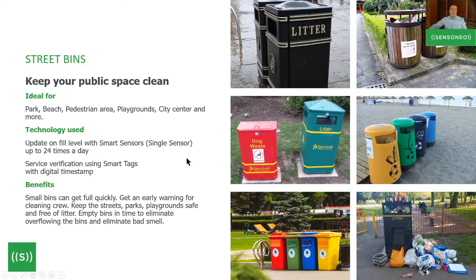Usually, we use single sensor for these use cases, in case there is availability of certain low power network, meaning our sensors support Sigfox, LoRa, NB-IoT connectivity. We also do support Bluetooth mesh networks, so streaming over advertising over Bluetooth. That's also possible. So a single sensor can support all of these. If there is a country that does not yet develop low power networks, or the coverage is limited, we can still use GPRS, but that only with the Quattro sensor, which is a little bit bigger than single sensor itself.